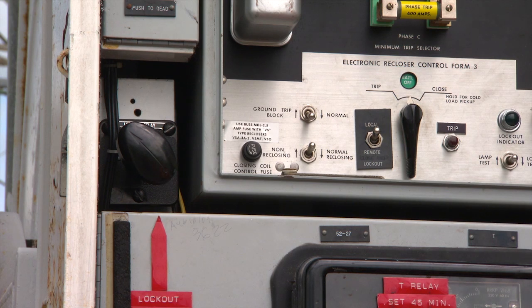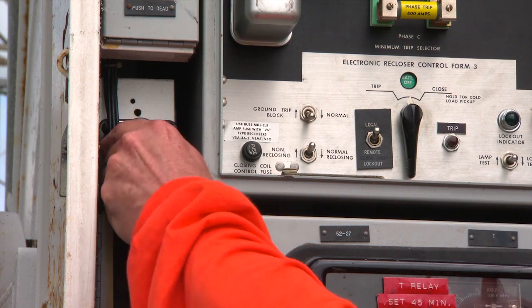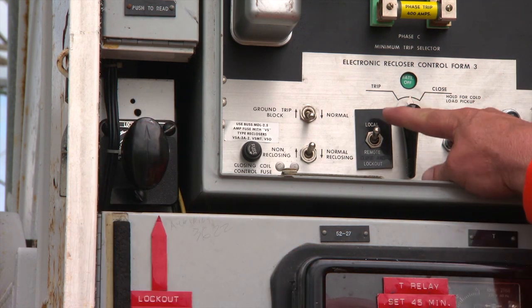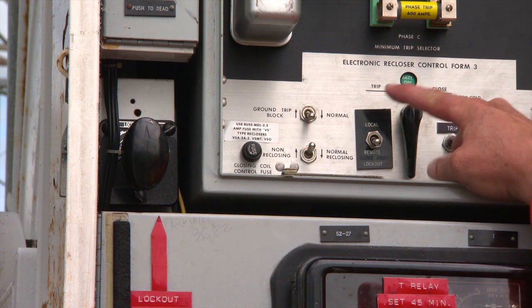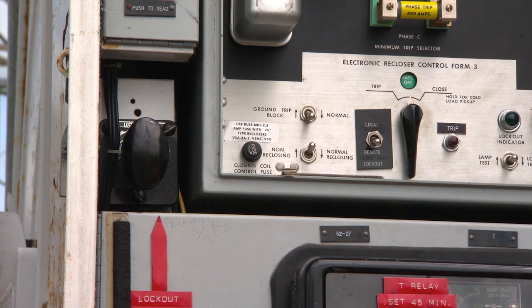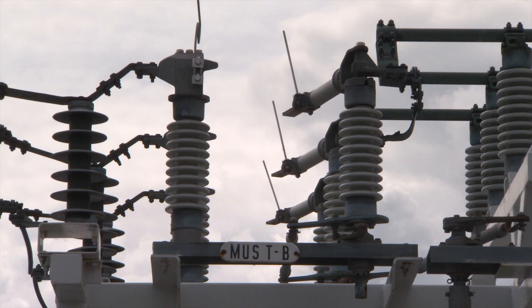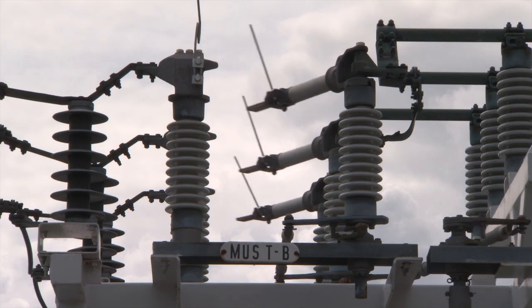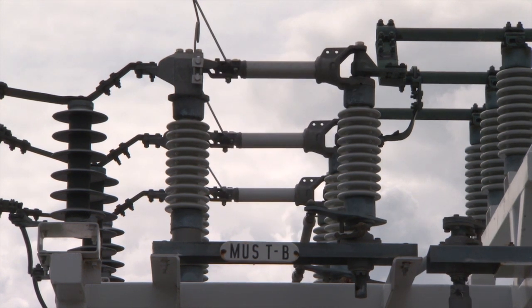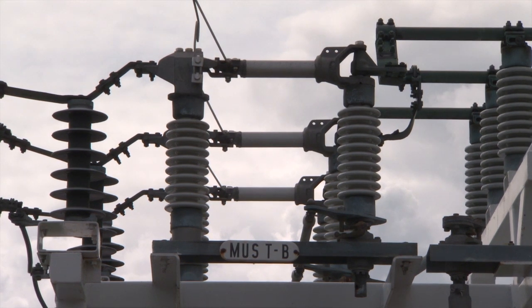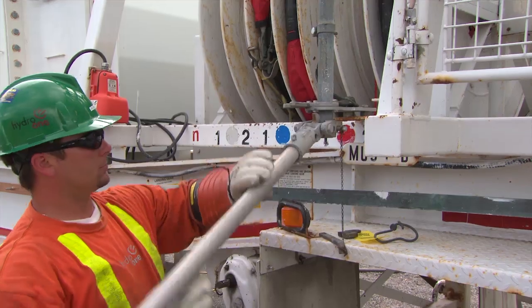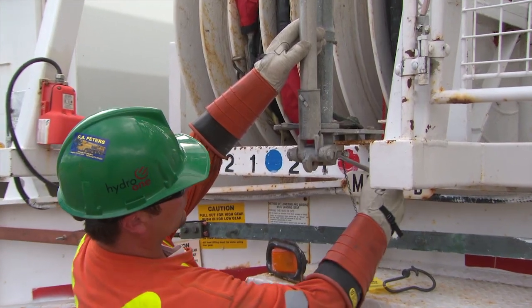Reset the MUS 86 lockout relay. Place the MUS F1 and F2 OCR local remote lockout switches in the remote lockout position. Check that the MUS low voltage disconnect switch is open and remove the work protection tag. Close and lock the low voltage disconnect switch. This energizes the low voltage bus and source bushings on both reclosers.